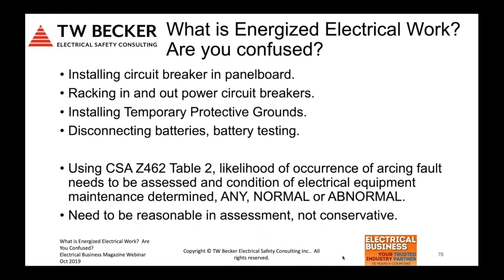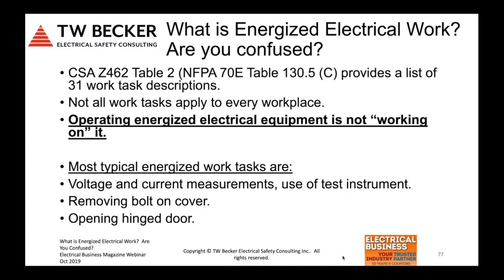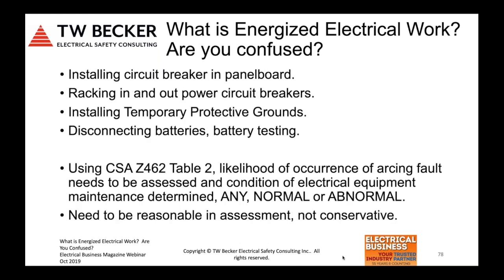Again, use that table, the condition of maintenance as normal or abnormal, and then it advises you of the likely occurrence of an arcing fault or arc flash as yes or no. So energized electrical work is diagnostic troubleshooting, repair and alteration. We want to eliminate the repair and alteration, and we want to sustain the diagnostics and troubleshooting, or the work tasks that are related to isolation, racking in and out power circuit breakers, and installing temporary protective grounds. So energized electrical work, we need to sustain it. We need to make sure that the risk is acceptable, and we need to make sure that we don't go down a rabbit hole with those myths and misinformation that debilitate us from using electrical energy and having workers that are qualified, competent and trained with qualification training or electrical safety training, understanding this work, and we have the right hierarchy of risk control methods applied to reduce risk to that worker when they do energized electrical work.